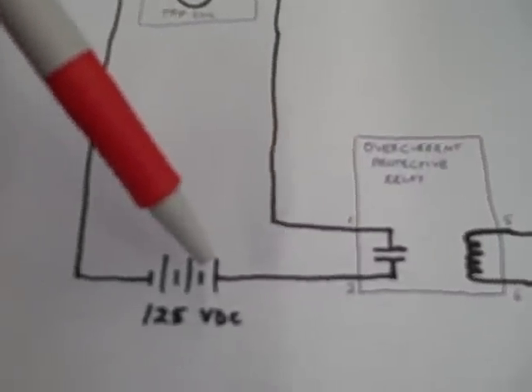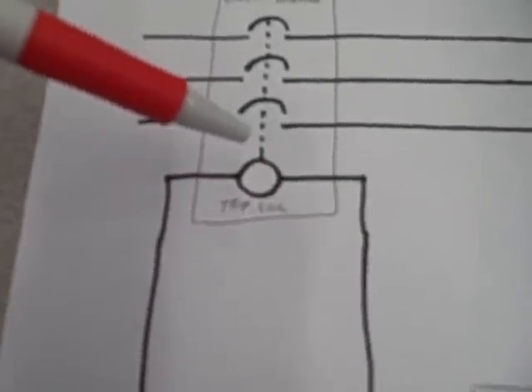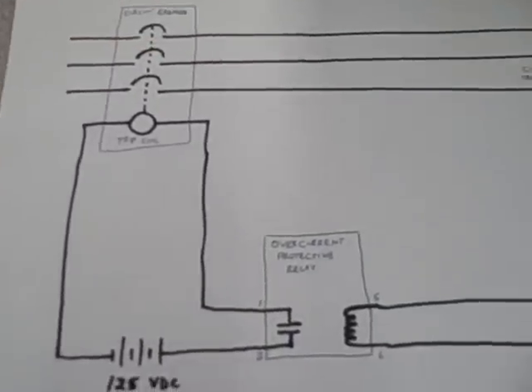Then that contact closes, sends 125-volt DC power to the trip coil on the circuit breaker, causing the circuit breaker to trip and to interrupt power in the three-phase system.